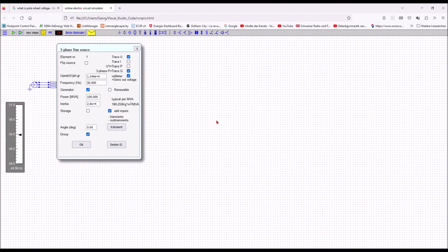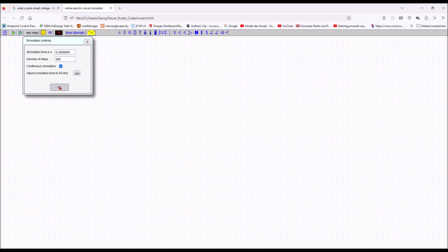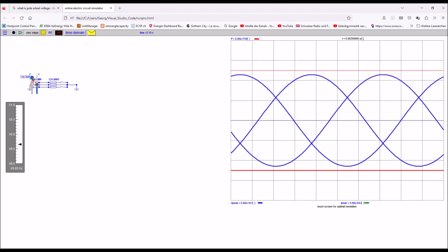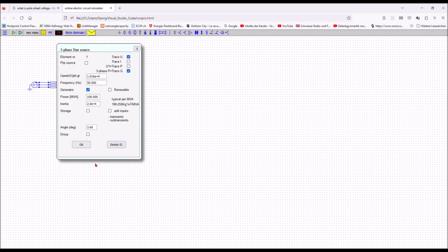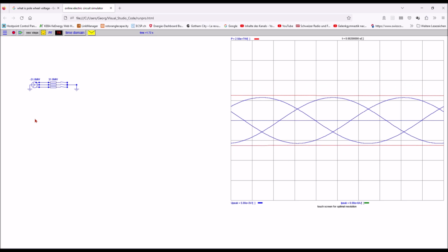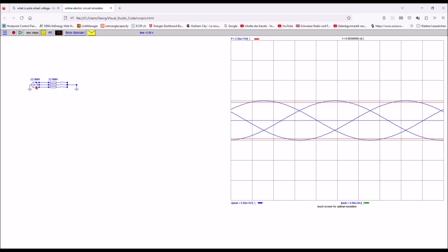I can also run the generator without inner transient reactance. In this case it is only a voltage source but with controllable torque. In this case the terminal voltage is equal to the pole wheel voltage. Or alternatively I can run the source including an internal transient reactance, but this time without torque control. So you can watch the interplay with other connected sources when you slide the angle of the source.